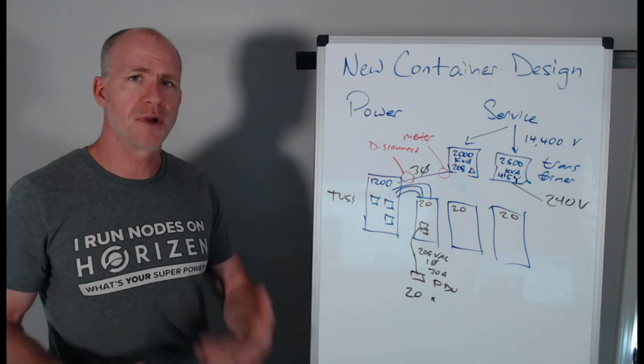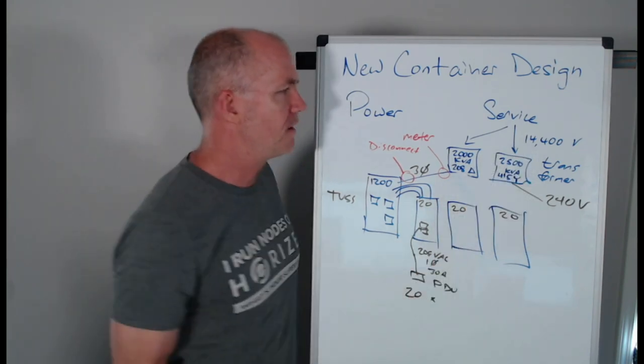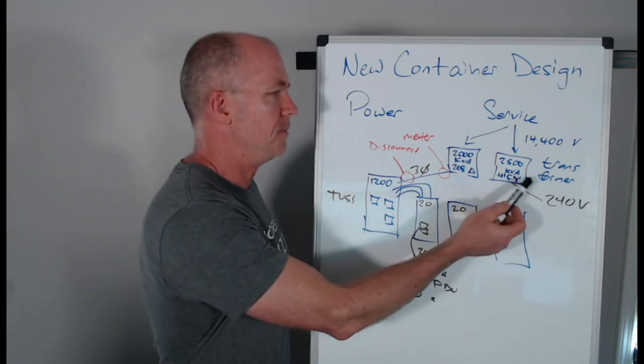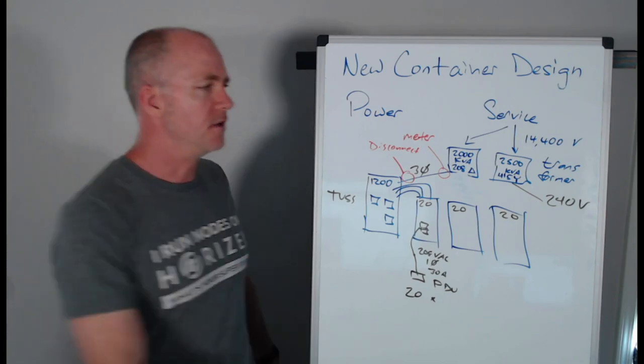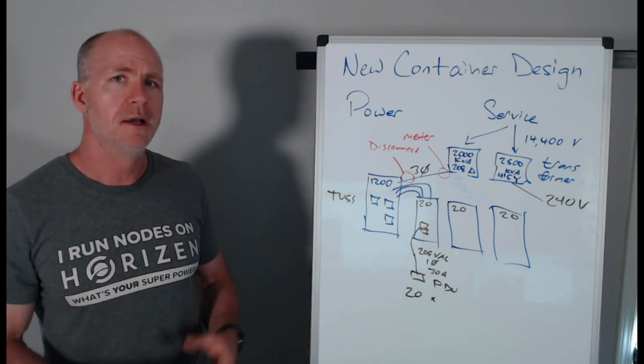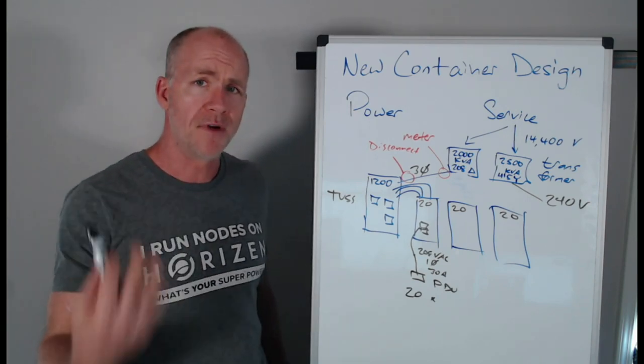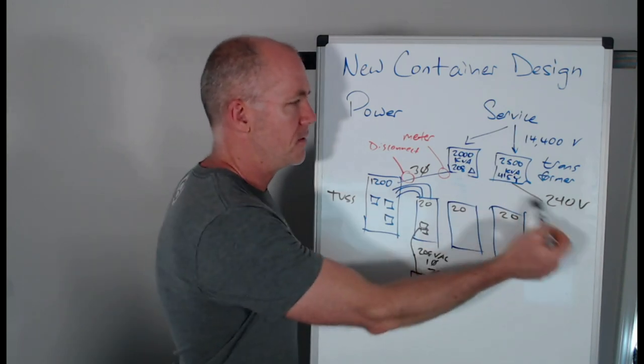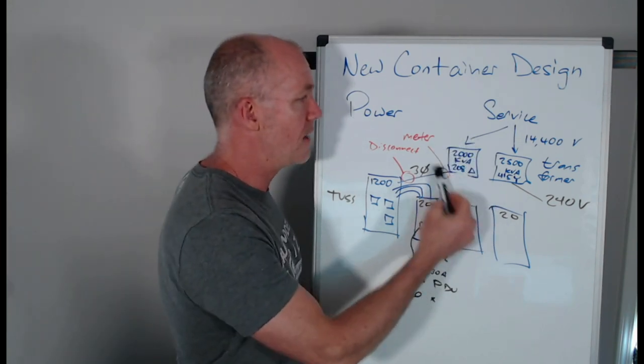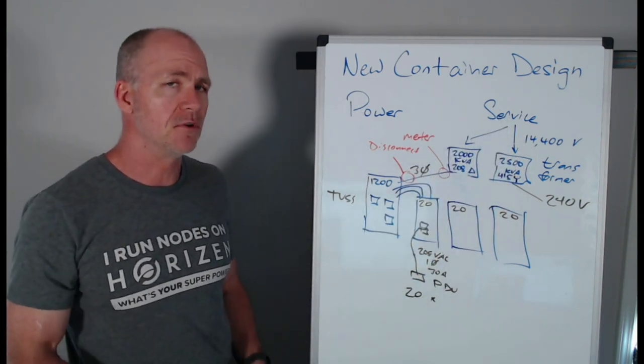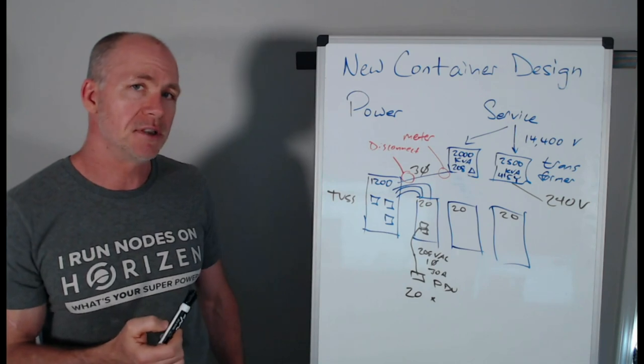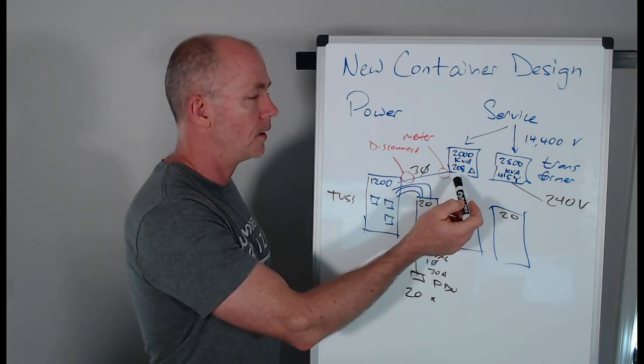And the transformer transforms the voltage to a lower voltage. So the sweet spot in the market, the best pricing and availability that you're going to get is if you get a 2500 KVA 415Y transformer. And when you do the Y is because you're planning on connecting from phase to neutral, and the phase to neutral connection will give you a 240 volt connection. I'm told this is a common type of transformer in Europe, Latin America, not as much here in the United States, but there are places that you can get them. So if you can provide your own transformer and then the power company hooks into that, then you have 240 volts coming off a phase to neutral connection. There's advantages to that. I'll talk to you about what I'm designing because what our power company does is they provide the transformer. You can only do the transformers that they provide. We're going to be looking to get a 2000 KVA 208 volt delta transformer.